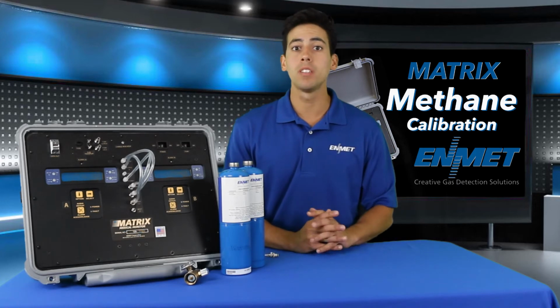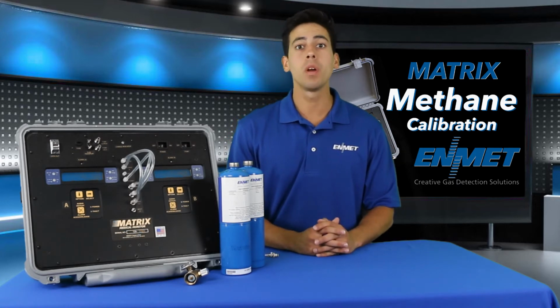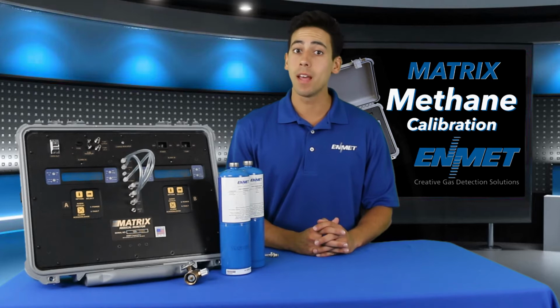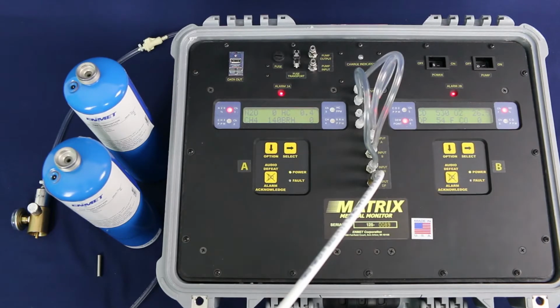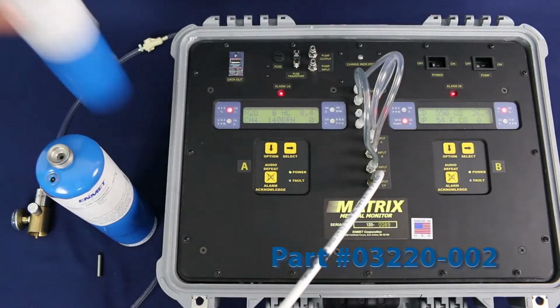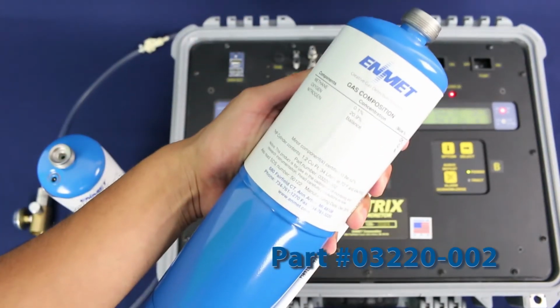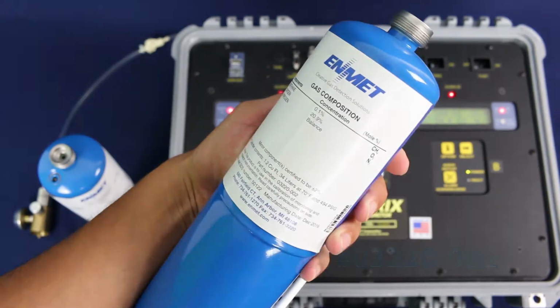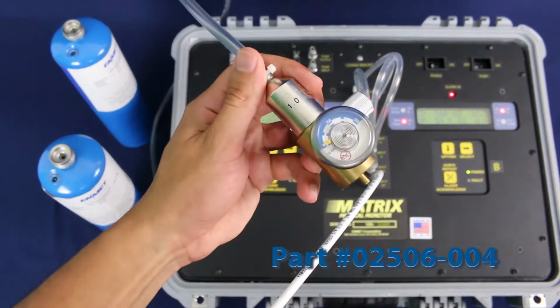Here we have a properly set up matrix unit that we are going to use to calibrate the methane or CH4 channel with. Before we start, you'll need two different gases for this calibration: 20.9% oxygen or clean compressed air and 0.1% by volume methane. You will also need a calibration adapter and a magnet.